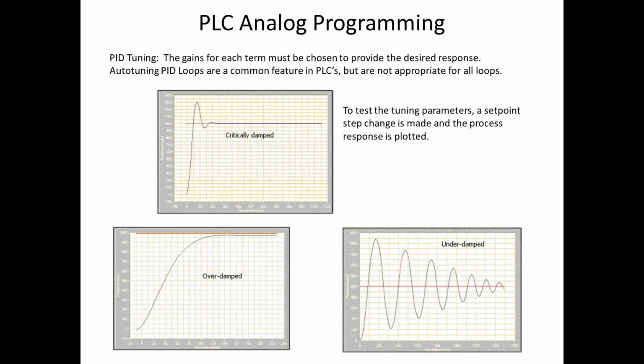But PID control is a main type of control used for PLCs, and once it's been instituted, it needs to be tuned. Tuning determines how well it dials in to the set point that you want. The classic critically damped process usually has the value overshooting the set point a little bit, coming back down, maybe undershooting it a little bit, and then coming back in and dialing in fairly quickly.